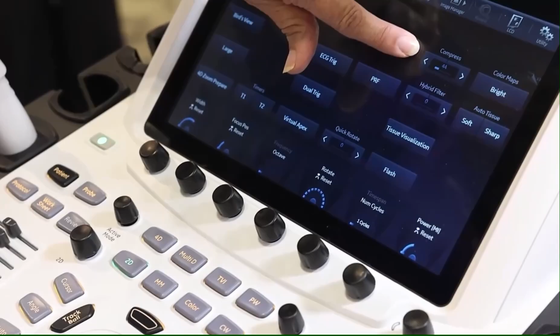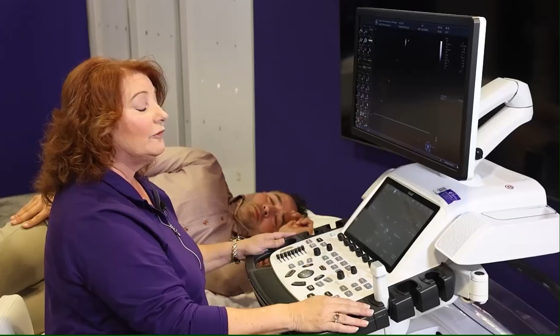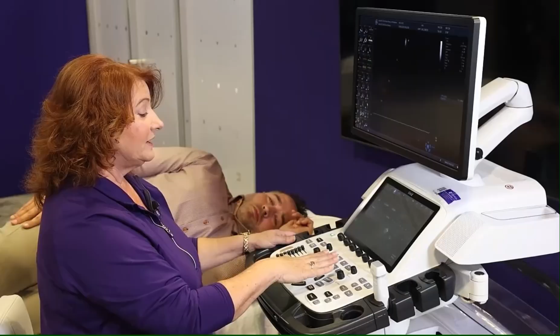Then we're going to be able to look at our compression. Compression is a parameter that makes our image look good, but it does not affect the working power of our bubbles. In other words, it does not disrupt the bubbles. Same thing with 2D gain. We will adjust those according to the needs with our patient. Also, we're going to look at our pulse repetition frequency correct for ultrasound imaging agents. And then the next settings we're going to look at is DDP, which is persistence, and then UD clarity, which is our speckle reduction parameters for our studies. Once those are set, you're ready to image.